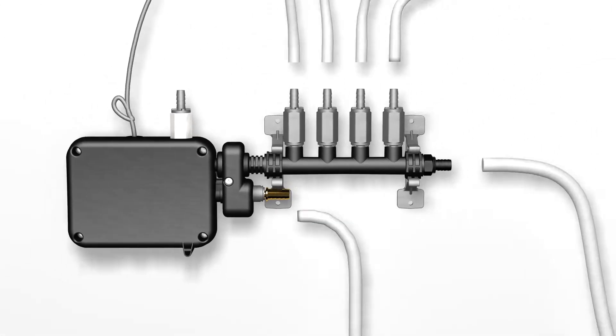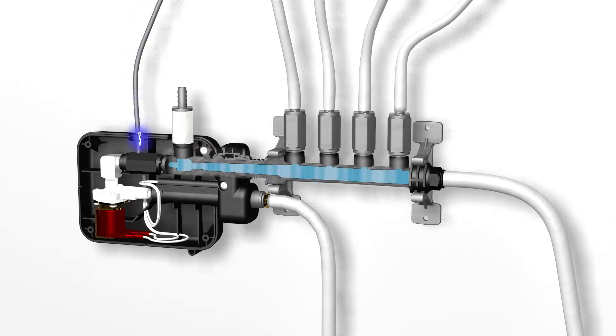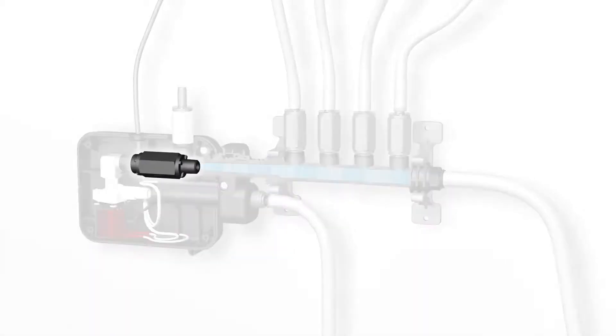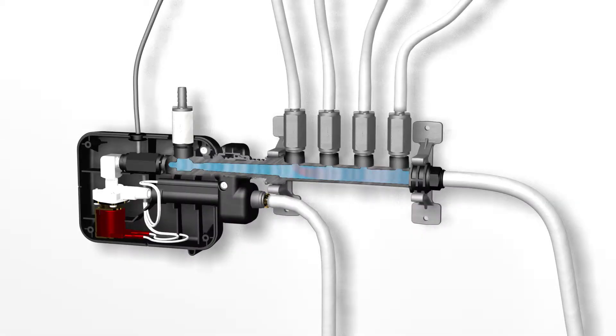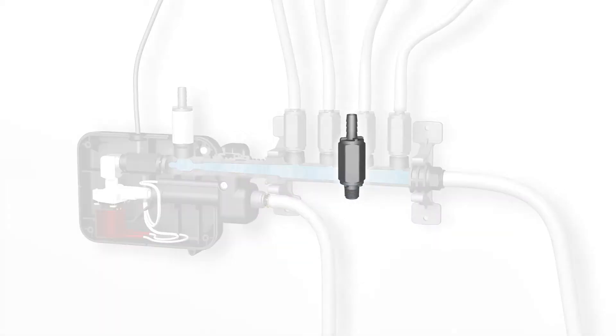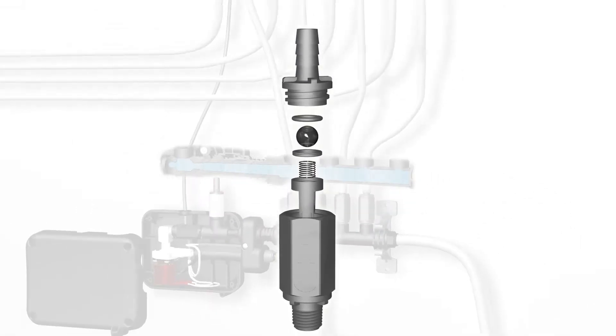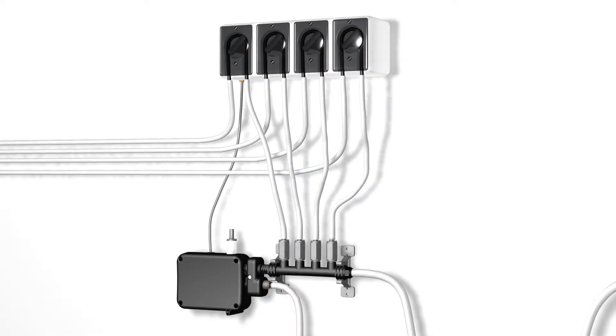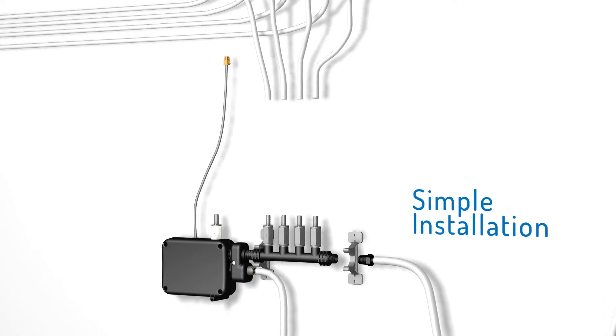The flush manifold uses water flow to mix and deliver liquid chemicals to their destination. As water flows up from the inlet, the flow switch checks that there is adequate water flow, and an inlet check valve prevents chemicals from flowing up the inlet. Once water flow is confirmed, the chemical pumps activate, sending chemical down the lines to blend with the water stream. A second set of corrosion-resistant check valves prevents unwanted chemical mixing and ensures long-lasting, problem-free performance.